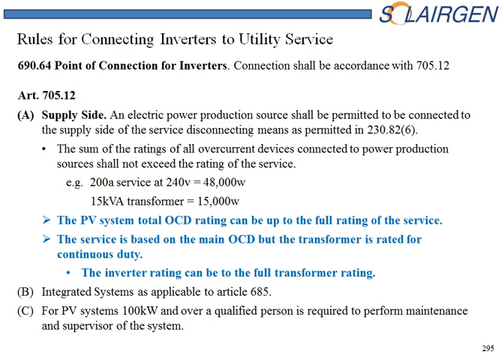First, let's look at the supply side, the utility side, line side connection. Whenever we're connecting into the utility side of the service, we can go up to the full capacity, 100%. The service states that the service size cannot be exceeded by 100% of the overcurrent device. So we'll have to look at the inverter overcurrent device capacity when we're looking at the service — that's the actual overcurrent device in the system.